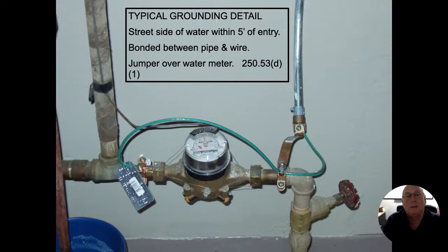Something else too, just throwing this out there, that tamper wire on that water meter, I kind of look for those. Many times you're going to find a tag on there where it's like a $500, $750, or $1,000 fine if that tamper wire is cut. I would guess around 20%, so 1 out of every 5, I find where either that tamper wire is missing or it's cut. Some communities don't require it, and some do, all right? But I would still let my client be aware of it. This way, they're not going to get stuck in case a meter reader comes inside and sees that that's missing. But for us, in this class, we're talking about the GEC.